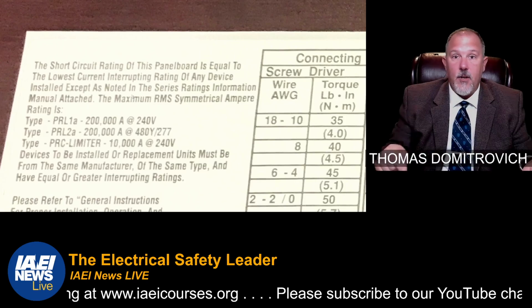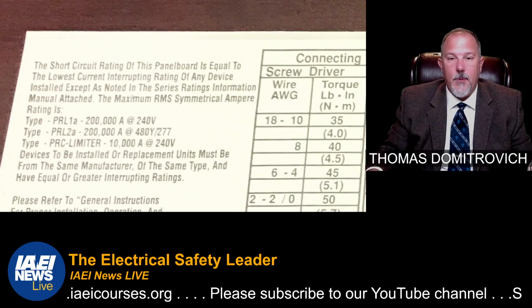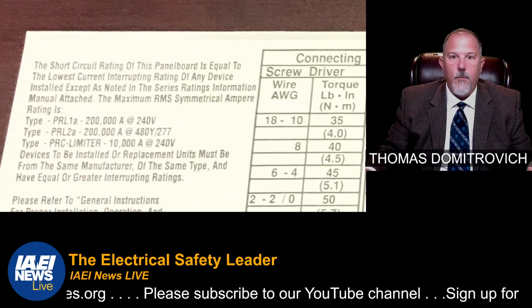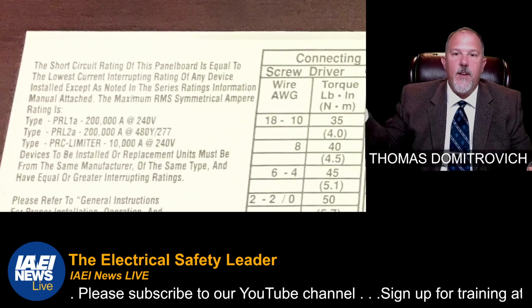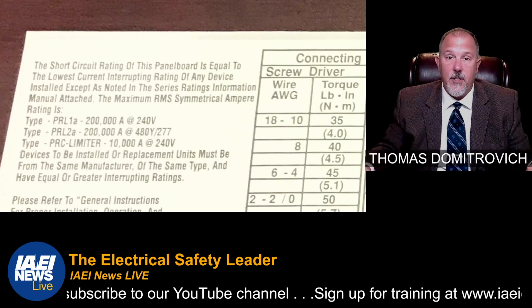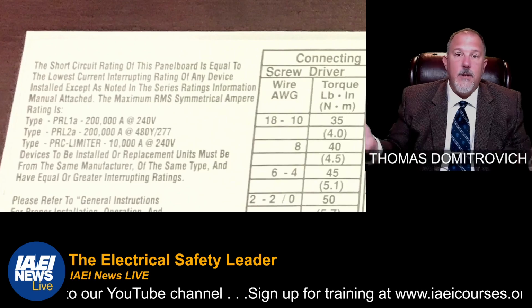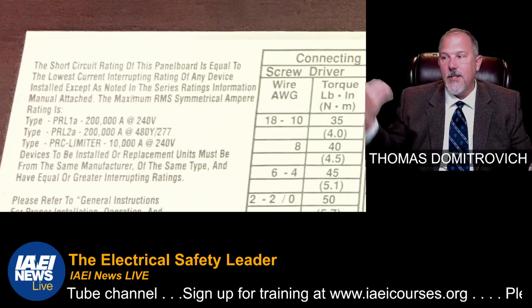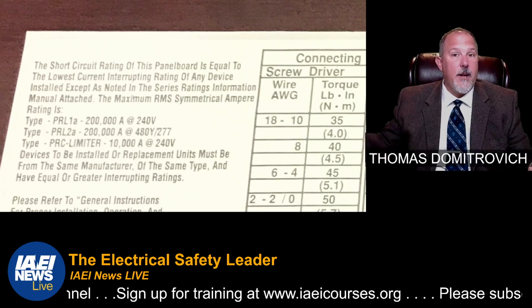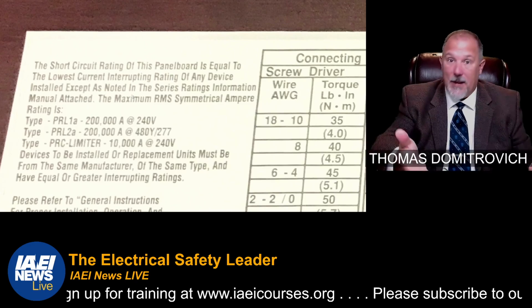If you bring the breaker with you, fine. If you just go down and say, hey, I need a 20 amp breaker, then they're going to go, well, what panel's it in? Well, I need a whatever catalog number for whatever manufacturer that you're dealing with. You tell him the load center it's going into. He goes out and gets you a 20 amp breaker. You think he's going to come back with a 22 or a 65K? He's going to come back with a 10K.